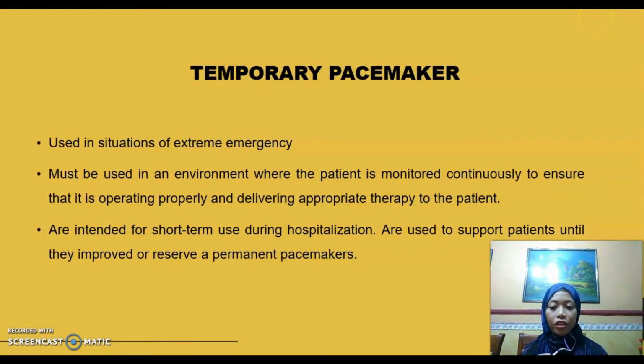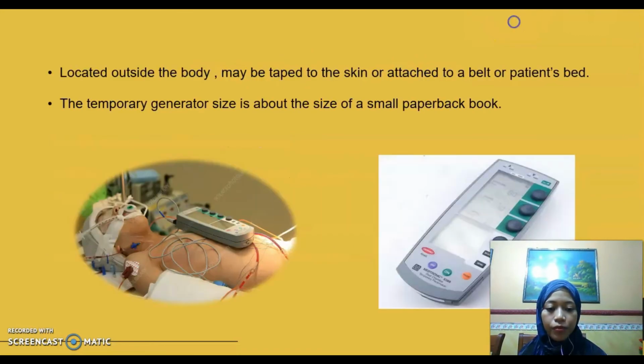Temporary pacemaker is used in situations of extreme emergency and must be used in an environment where the patient is monitored continuously, to ensure that it is operating properly and delivering appropriate therapy to the patient. It is intended for short-term use, to support patients until they improve or receive a permanent pacemaker. It is located outside the body, and may be taped to the skin or attached to the patient's bed. The temporary generator is about the size of a small paperback book.